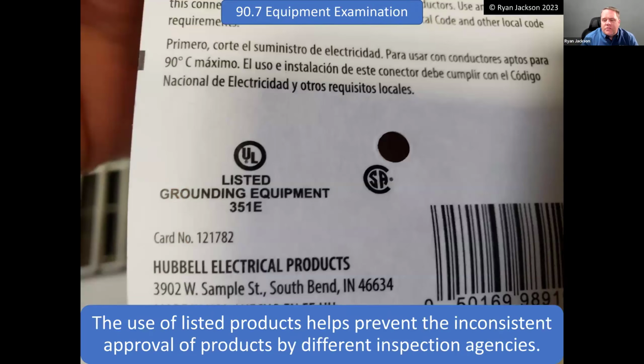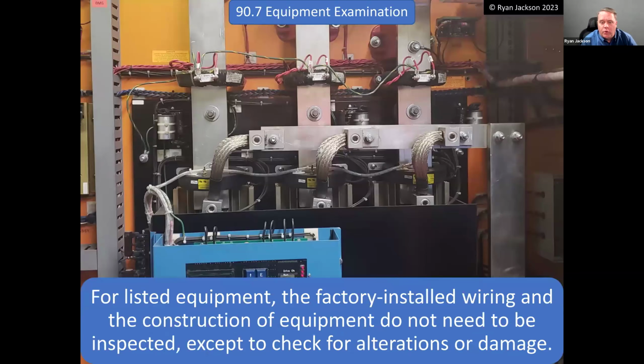The use of listed products helps prevent the inconsistent approval of products by different inspection agencies. So imagine if, as inspectors, we had to determine the suitability of every single product that gets installed. It wouldn't be possible. And quite frankly, we're not qualified to do it, and we don't have the facilities to do it. So we rely on testing agencies like UL and like Intertek, right? They can test the products, make sure that they're going to work properly, and more importantly, make sure they're going to fail safely, right? So the use of listed products really provides for consistent approval across the board.